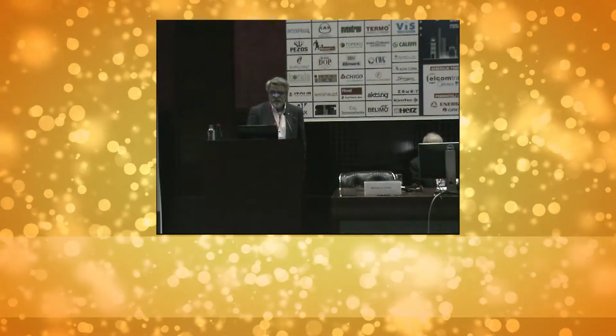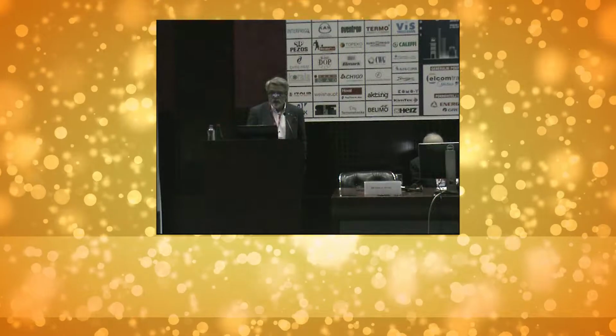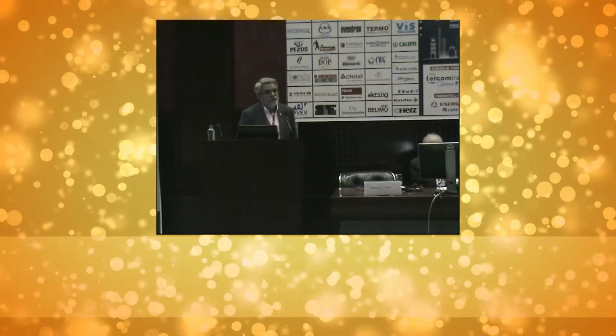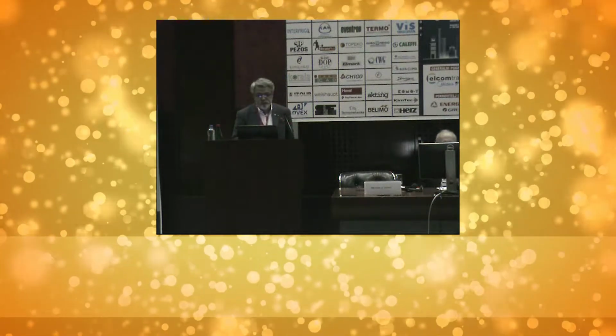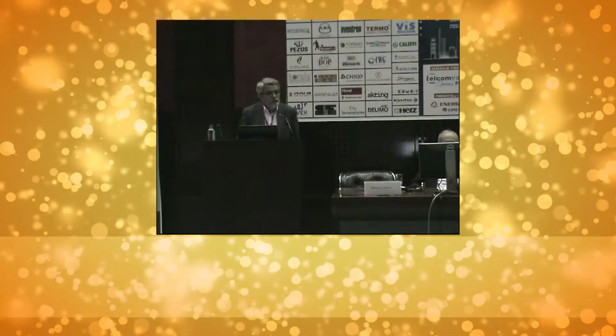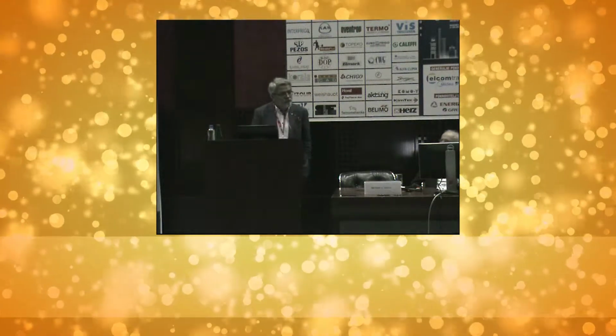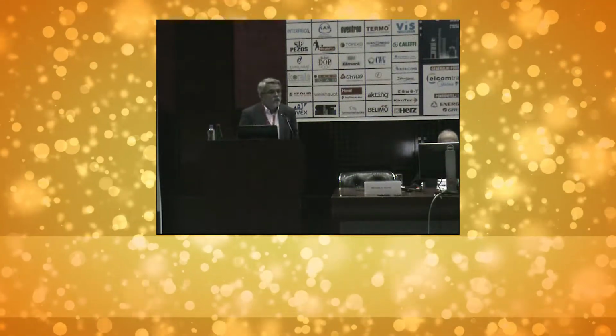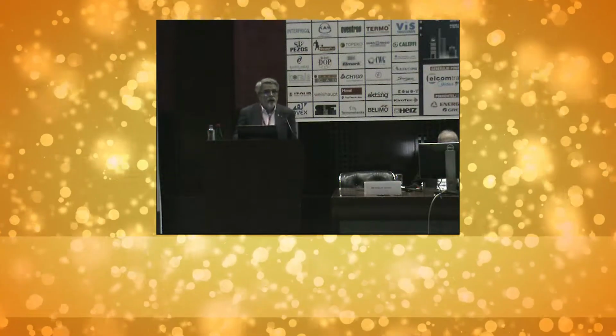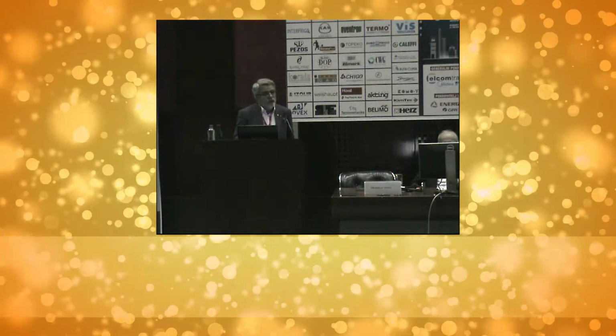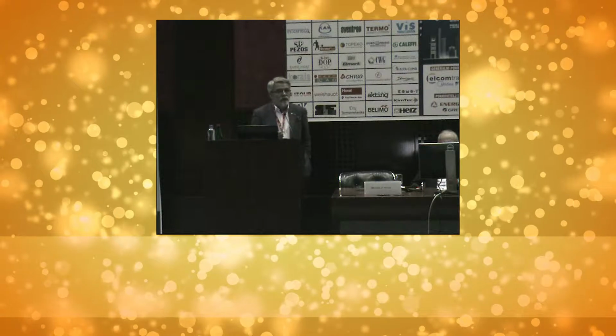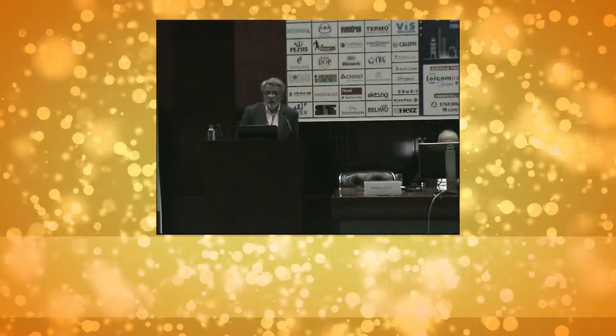we have to achieve for hockey a hard ice, which is usually between -5 and -7 degrees Celsius. For artistic or figure skating, it's -3 to -4 degrees Celsius. That means a dry ice. For leisure it would be -1 to -3. It's usually a soft ice or a humid ice.